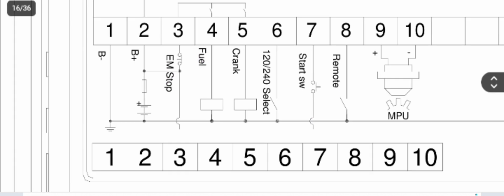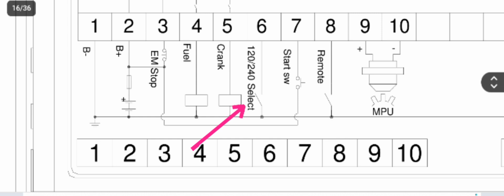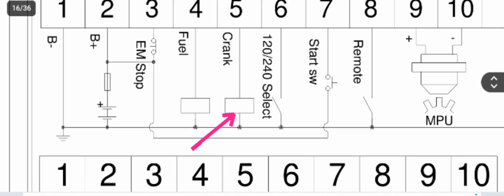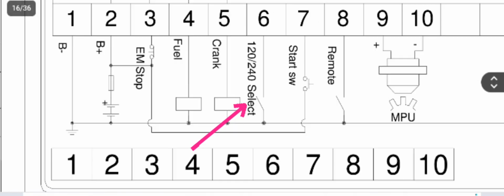After that, pin number 6 is the 120 and 240 voltage selection. If you want to select the voltage for this controller's input supply, closing this contact will show 120 and opening it will show 240.